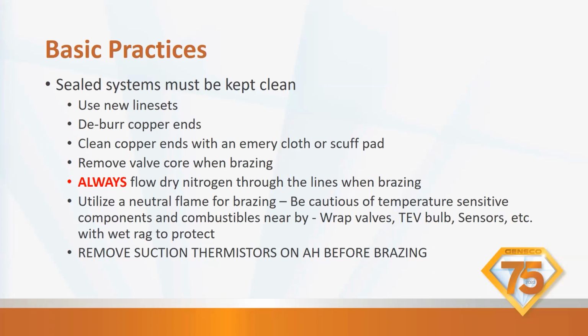Always flow dry nitrogen through the lines anytime you're brazing. When you're installing a piece of equipment and you roll out your line set, you set your outdoor unit, you set your indoor unit, don't cut the line set and don't open the line set to the atmosphere until you're ready to braze. What I always did was I got it in position. I did all my bends. I got it ready. I didn't take the caps off the end until I was ready to unplug the line set, take the cap off the indoor unit, and plug in the line set.